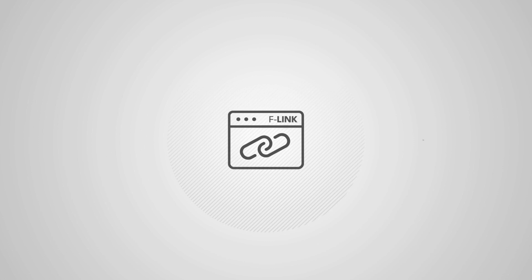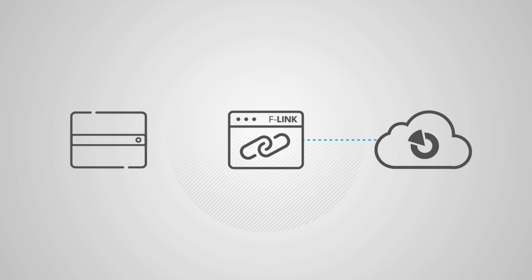Constant communication between F-Link and the cloud is established. F-Link communicates directly with the cloud, and if your computer with F-Link is not connected to the internet, then the control panel is used as a hotspot. According to the installer's rights, which he has in the cloud, F-Link creates a form for registration and pre-fills the data such as serial number, etc. For registration, it receives data from the cloud and sets it in the control panel locally. When the installation is finished, the installer must end service mode and unplug the USB cable for correct downloading of the control panel settings. This registration can be made also remotely by F-Link if persistent communication LAN is set.